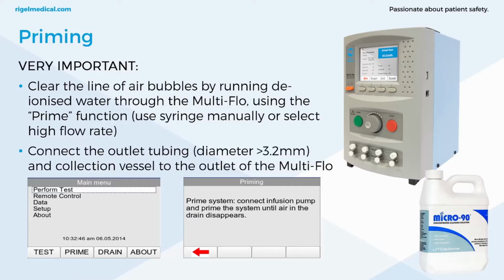So to carry out the test, use a syringe manually or select a high flow rate on the infusion device. Typically we use a syringe, and then we can prime the device using that, and then I'll show you how to do that on the next few slides. So to prime the system, from the main menu you just select prime, really simple.